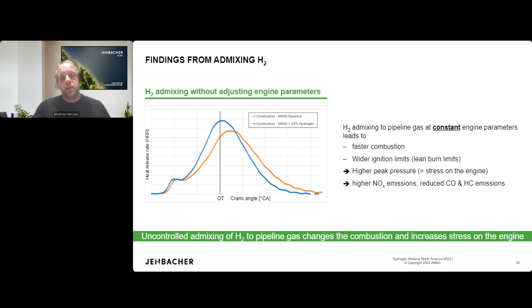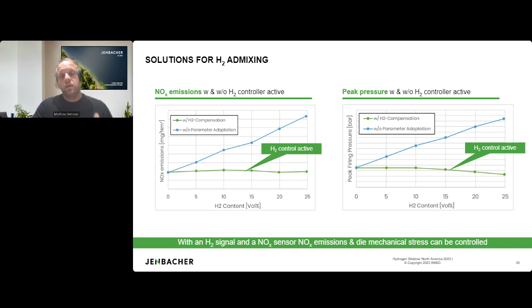Therefore, we utilize an H2 sensor system and software compensation package, and we can modify the key parameters of the engine so that independent of the H2 concentration up to 25%, we maintain NOx emissions and peak firing pressure at the same limit or even lower compared to natural gas operation. Key here is we need to know the concentration of H2 and the software package—how did we develop this?